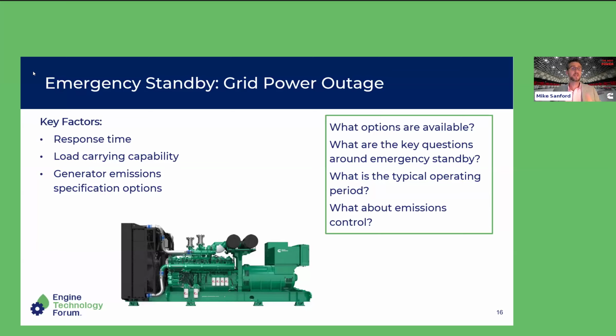The switch gear that feeds the normal source of power to the loads actively monitors the condition of the utility, the normal source of power. When it detects that this source is no longer adequate for the site, meaning the voltage or frequency has deteriorated sufficiently that the loads can't operate normally, it initiates a transfer.